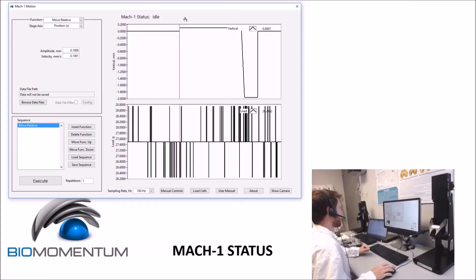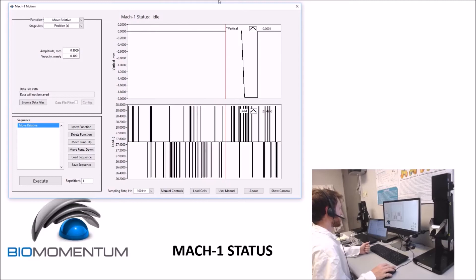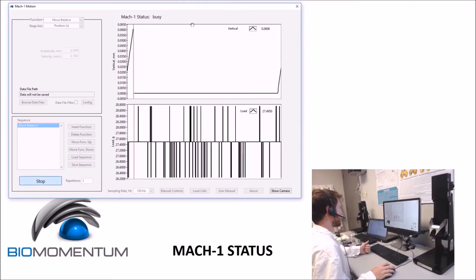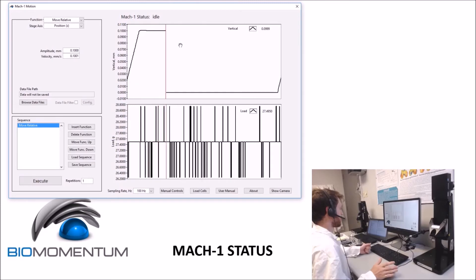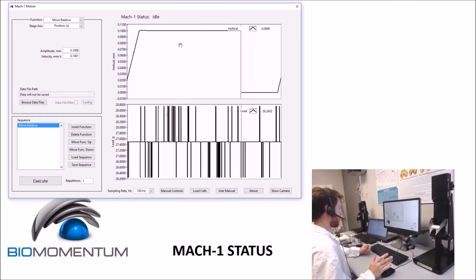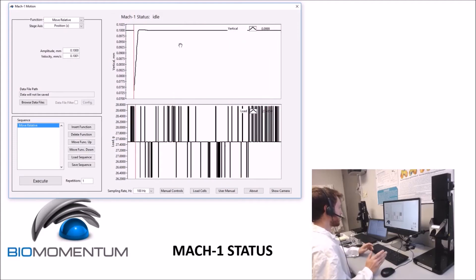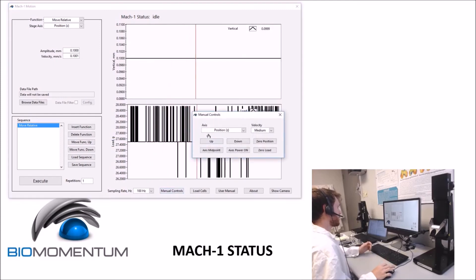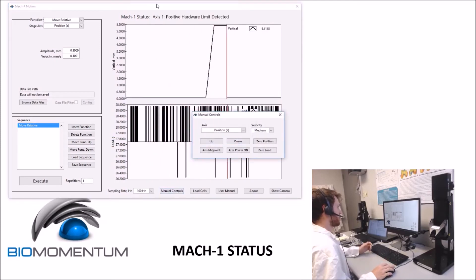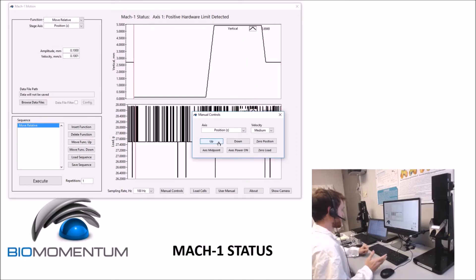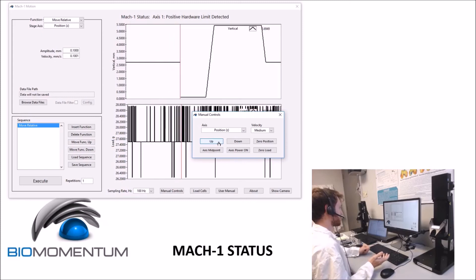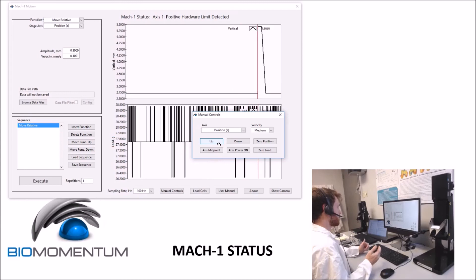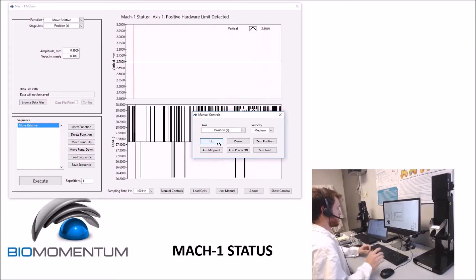The top line on the panel indicates the status of the Mach-1. The normal messages that will be shown are idle when the system is not in use, and busy when a sequence is running. Error messages and notifications will also be shown here. Some possible messages are following error threshold exceeded, when the controller was unable to keep track of the stage's position. Positive and negative hardware limits detected, for example. Maximum velocity exceeded when the maximum velocity of the stage was reached and the stage will stop moving, as well as maximum acceleration exceeded when the maximum acceleration of the stage was reached and the stage will stop moving.